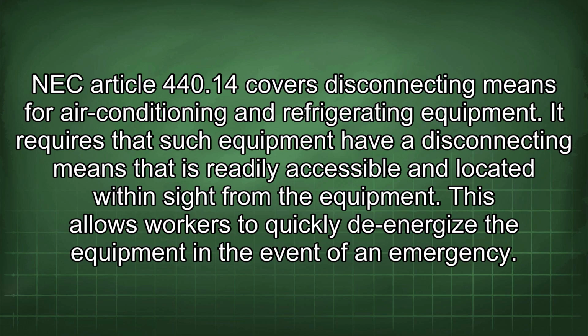NEC Article 440.14 covers disconnecting means for air conditioning and refrigerating equipment. It requires that such equipment have a disconnecting means that is readily accessible and located within sight from the equipment. This allows workers to quickly de-energize the equipment in the event of an emergency.